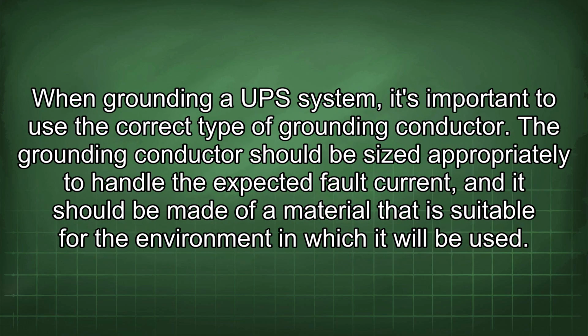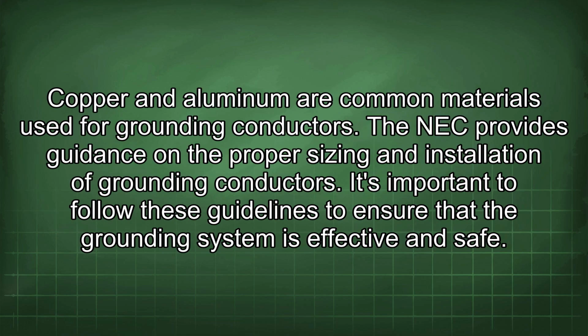When grounding a UPS system, it's important to use the correct type of grounding conductor. The grounding conductor should be sized appropriately to handle the expected fault current, and it should be made of a material that is suitable for the environment in which it will be used. Copper and aluminum are common materials used for grounding conductors. The NEC provides guidance on the proper sizing and installation of grounding conductors. It's important to follow these guidelines to ensure that the grounding system is effective and safe.